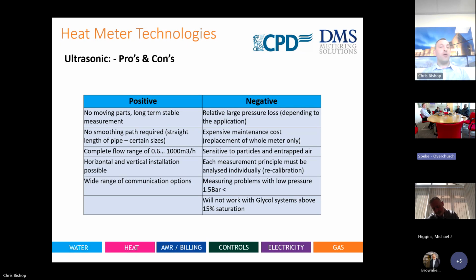So ultrasonics have no moving parts. That basically means they're a long-term stable measurement. A lot of European manufacturers state at the moment, depending on country regulations and recalibration approvals that's currently happening in the UK, 10 to 15 years is about an average life cycle for a heat meter. That would be an estimate based on how long a heat meter should be installed for. It still needs to be maintained on a yearly basis, or whatever the building profile is, maybe 2 years maximum. But recalibration is a 10-year cycle.